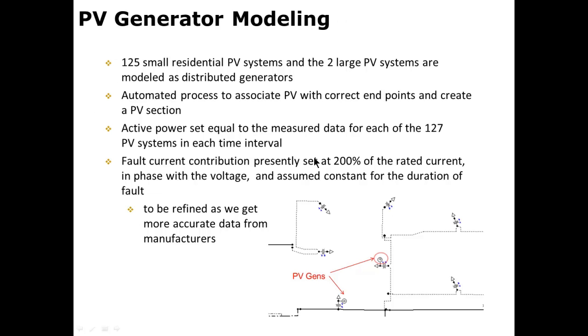Then the PV generators. All the 125 rooftop PV systems as well as the 2 large PV systems are modeled as distributed generators. OpenDSS supports that, and CYMDIST also models them as electronically coupled generators. As described earlier, we have an automated process to associate PV with their correct endpoints and create a PV section for the individual generators. The active power output of the PV is set equal to the measured data for each of them, and where measured data is not available, it is estimated using data from other inverters and weather station data.